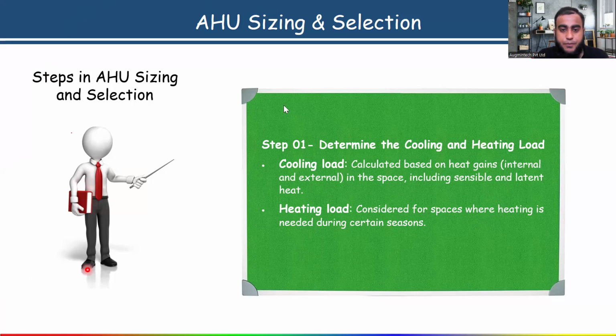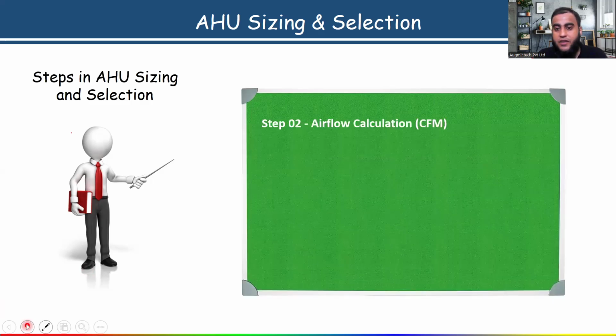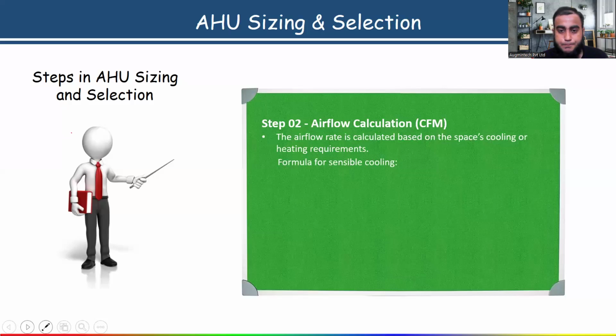Now, the next step which we have to discuss here for AHU sizing and selection is airflow calculation in cubic feet per minute. CFM stands for cubic feet per minute, because here I am showing you the sizing and selection in imperial units. Imperial means if you're working in feet, inch, pounds, that is your imperial unit. If you're working in millimeter, meter, centimeter, that is your metric unit. So the second step, after determining the heating and cooling load, is to calculate the airflow rate.